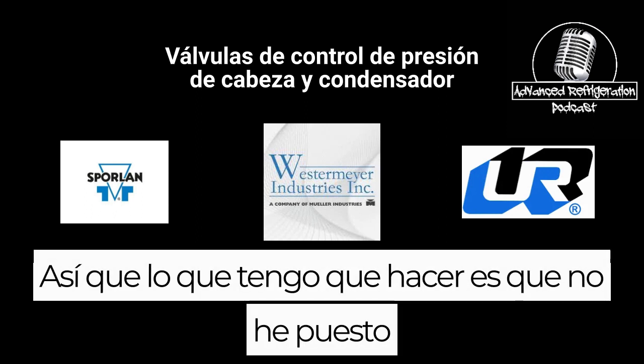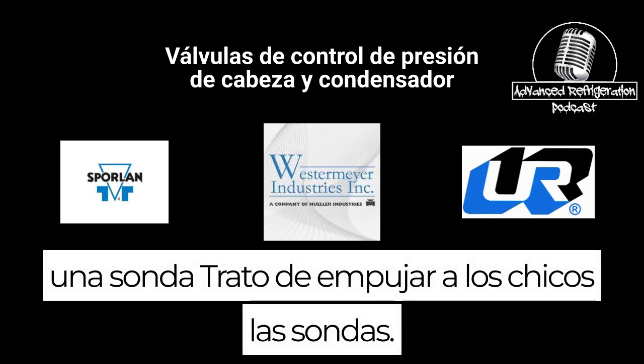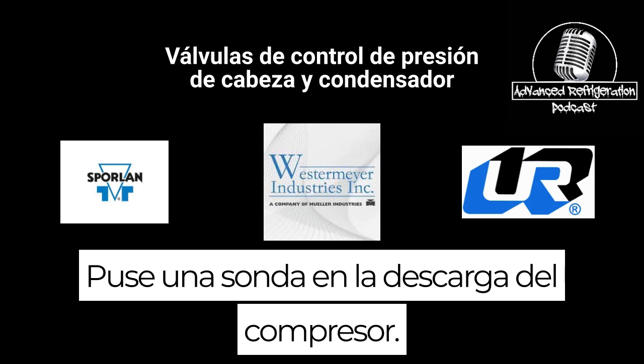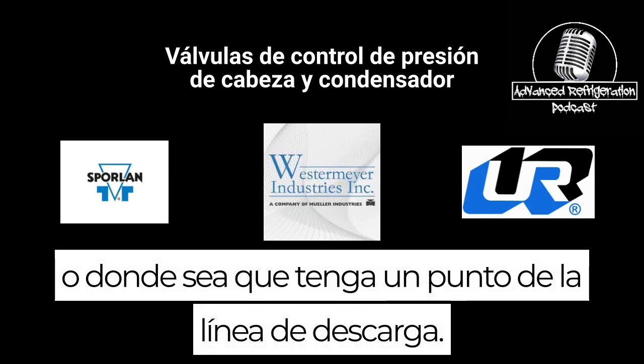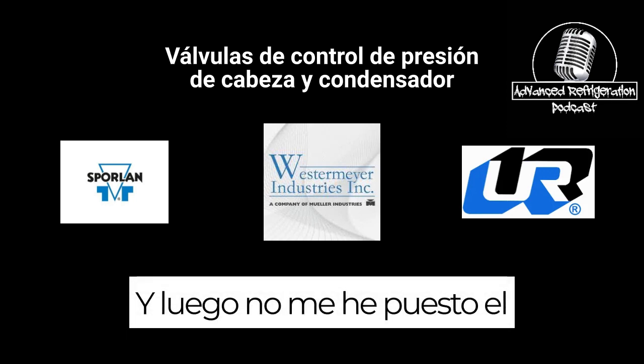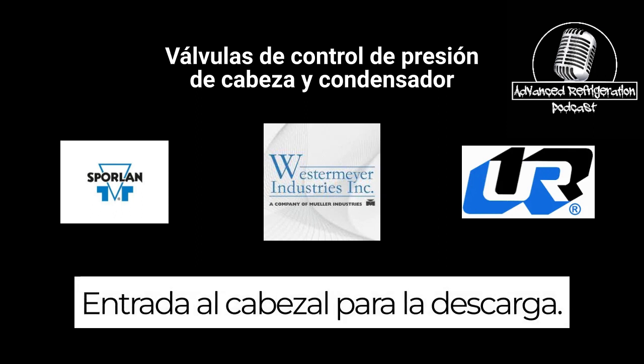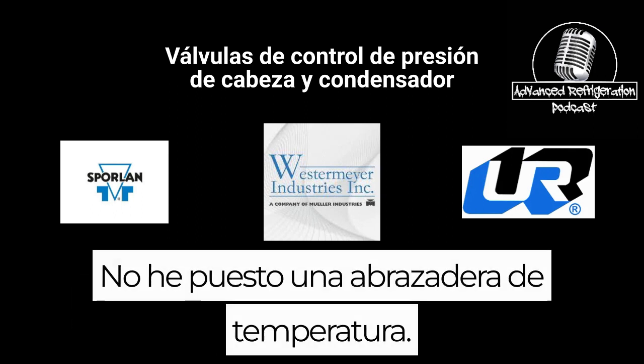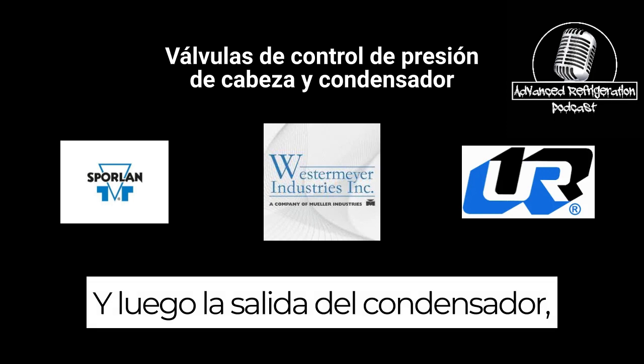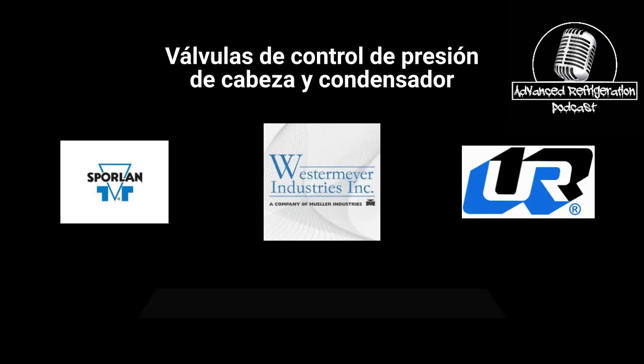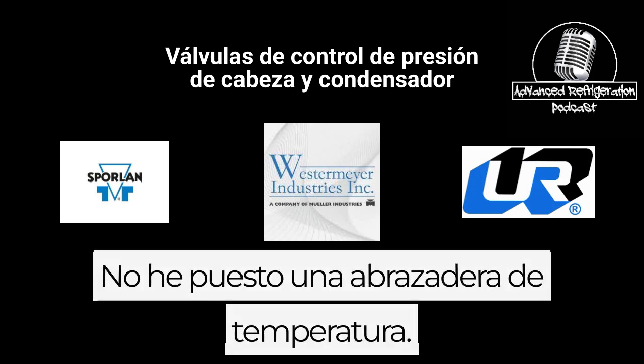So what I have guys do is I have them put a probe. I try to push guys at the probes. I put a probe on the discharge of the compressor, or wherever you have a spot in the discharge line. And then I have them put a temp clamp on the inlet to the headmaster for the discharge. And on the outlet of the condenser, I have them put a temp clamp, and on the inlet to the receiver, I have them put a temp clamp.